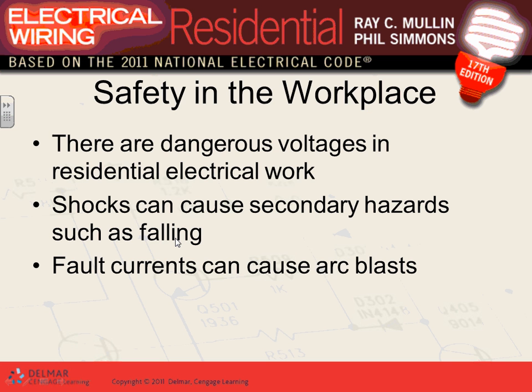I always used to say that in residential we don't do a lot of design, until I visited with BKV. You can't believe how busy these guys are just doing high-level apartments. You will walk into a riser building that has a 3,000 amp service, and all it feeds is just apartments. 3,000 amp service at 208/120. So there are a lot of amps in residential. Don't think of residential as just the house you're working on; think of all the apartments.